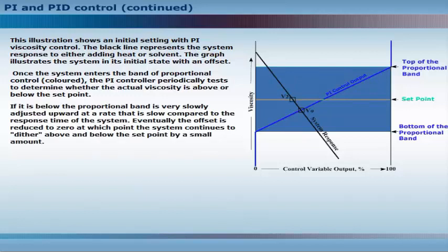If it is below, the proportional band is very slowly adjusted upward at a rate that is slow compared to the response time of the system. Eventually the offset is reduced to zero, at which point the system continues to dither above and below the set point by a small amount.